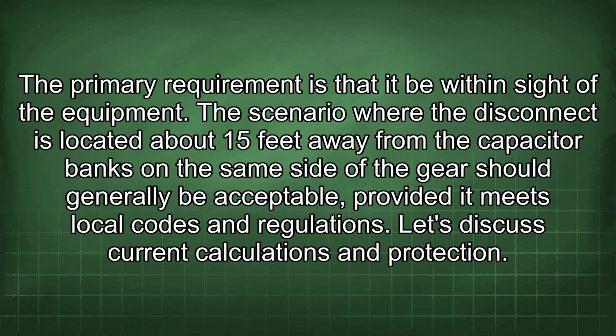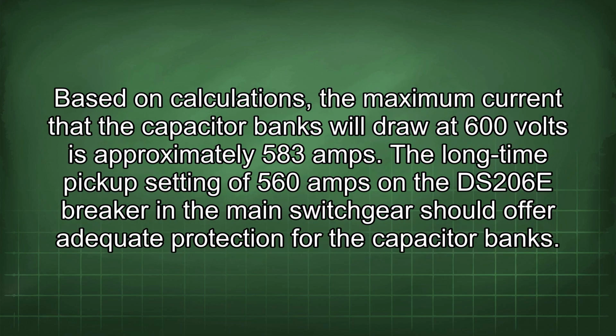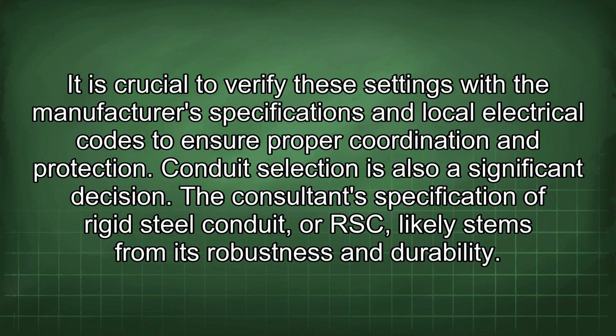Let's discuss current calculations and protection. Based on calculations, the maximum current that the capacitor banks will draw at 600 volts is approximately 583 amps. The long-time pickup setting of 560 amps on the DS206E breaker in the main switchgear should offer adequate protection for the capacitor banks. It is crucial to verify these settings with the manufacturer's specifications and local electrical codes to ensure proper coordination and protection. Conduit selection is also a significant decision.